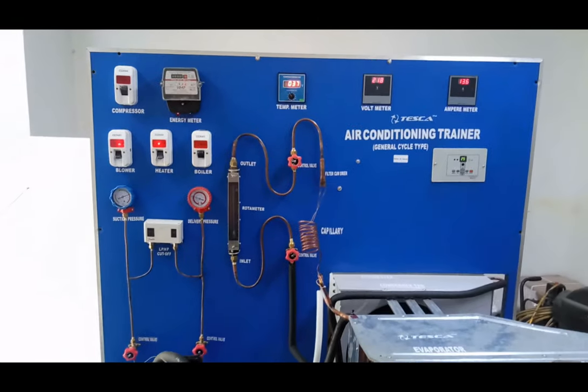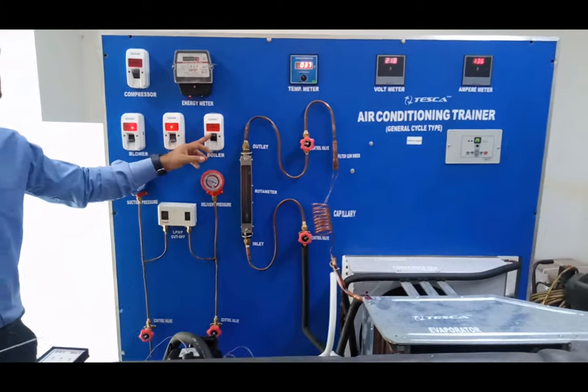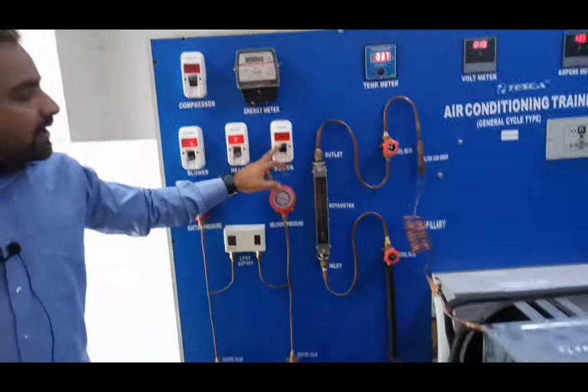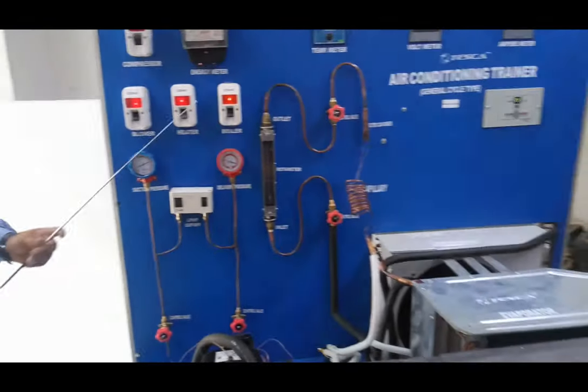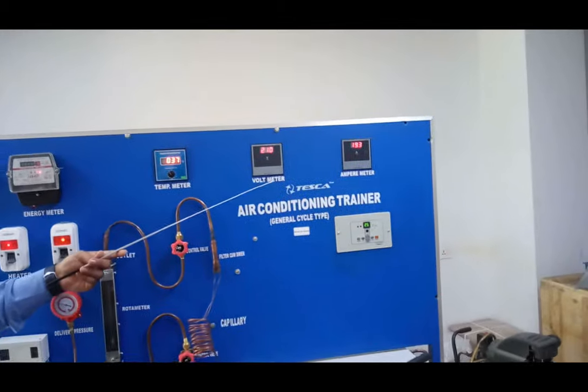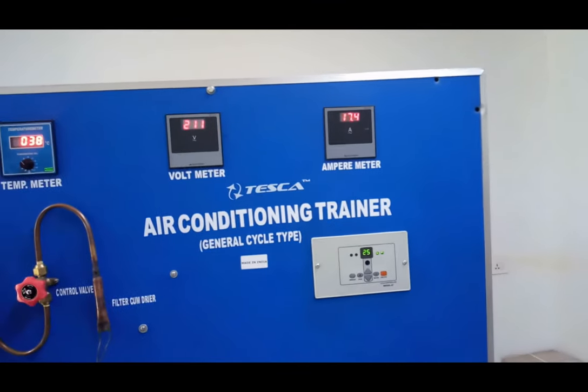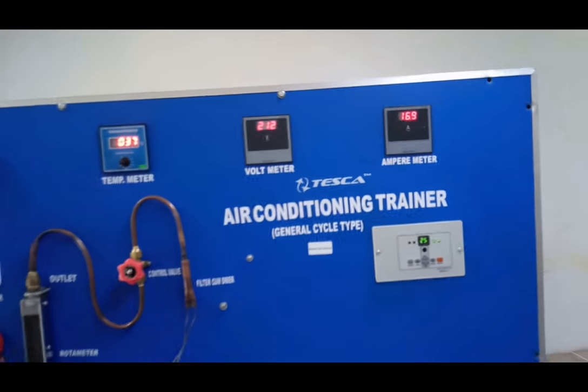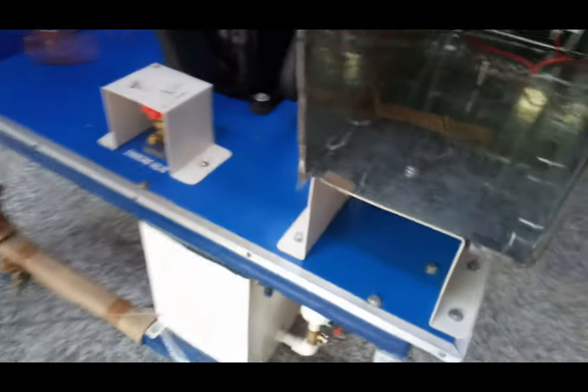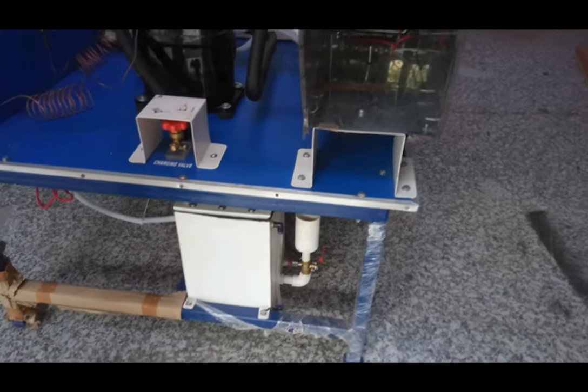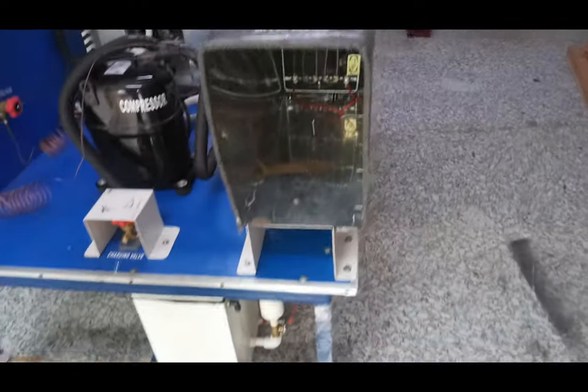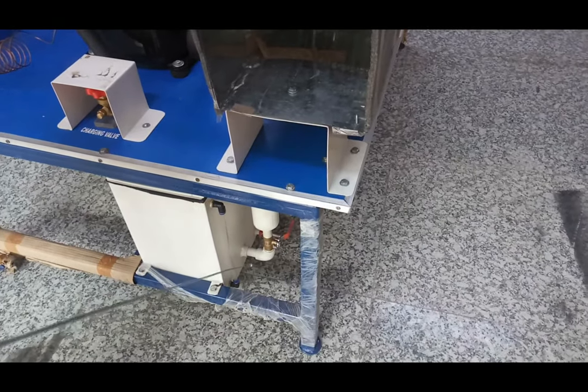Now for humidification, the boiler is provided in this panel. The boiler on-off switch is here. We can turn on the boiler switch. The boiler is on and we can see the load changes — it has increased at the ammeter because the boiler has started. The boiler is located at this location. Always make sure the boiler is filled with water before starting it. The steam generated through this boiler is supplied inside the air duct.